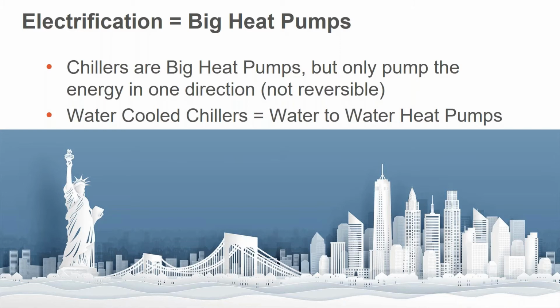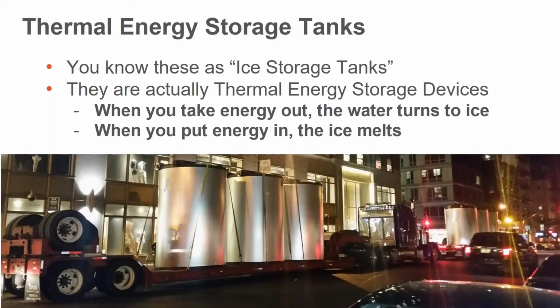So the first thing to think about is that chillers are big heat pumps. Electrification means big heat pumps, or that's what it certainly does to me. And chillers are big heat pumps. The big difference is that they're not reversible. The evaporator is always the evaporator, the condenser is always the condenser, but it's going one direction. And big water-cooled chillers are big water-to-water heat pumps. So we hear about ground source heat pumps and air source heat pumps. And really, it's almost a misnomer to call these things heat pumps. They're actually energy pumps. They pump energy from one temperature level to another temperature level. And I think for people that are not on the technical side, sometimes that helps.